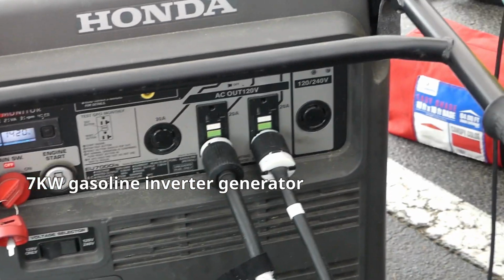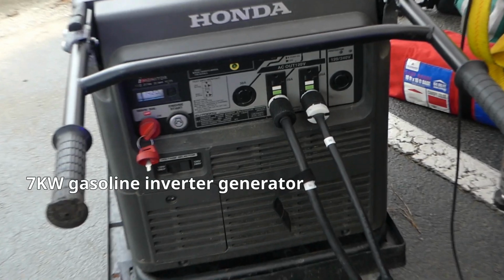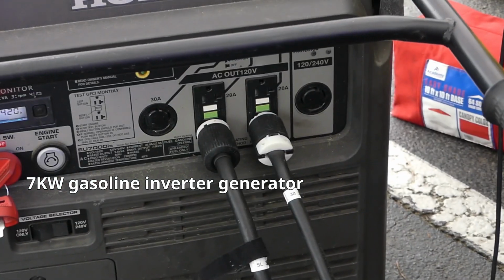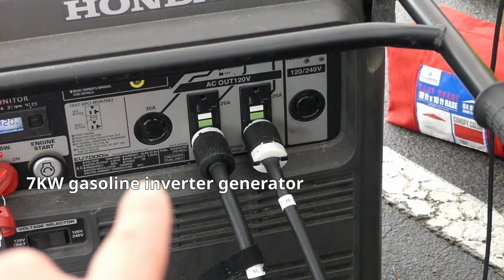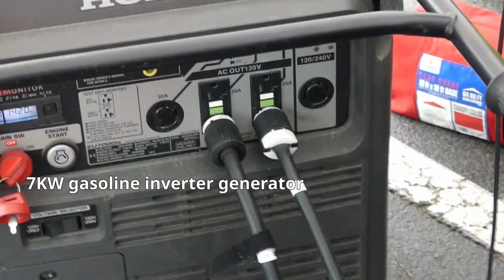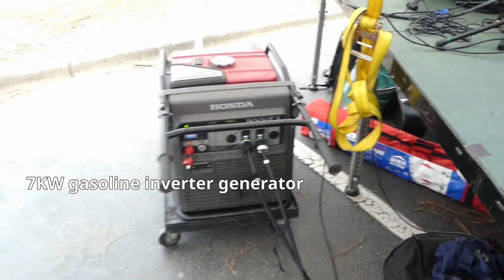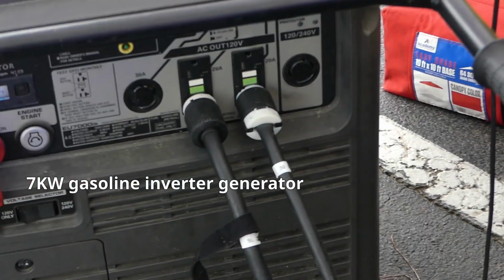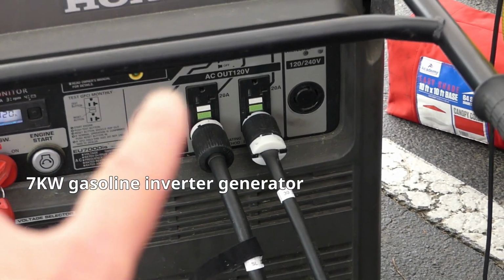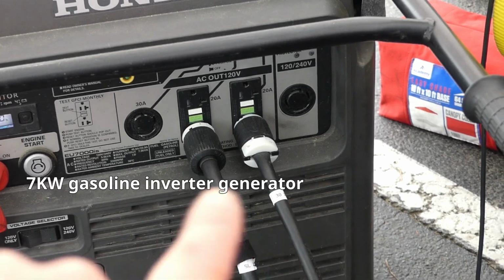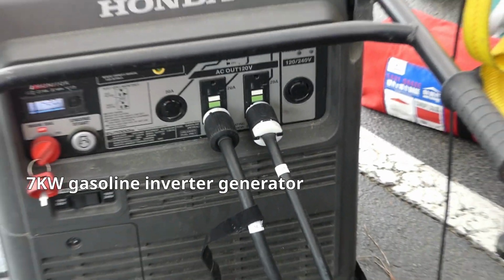And for this particular event, we were using 2 of the 20 amp circuits. And so that gave us 2,400 watts per circuit, so almost 5,000 watts of power. So one circuit was used for all the lighting, the front of house console, front of house tops, and band amplification, and the other circuit was used for the subwoofer amp.